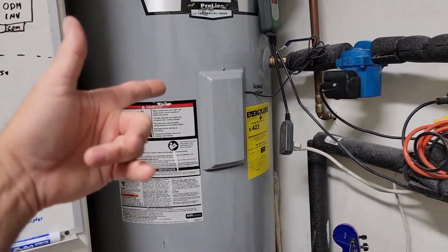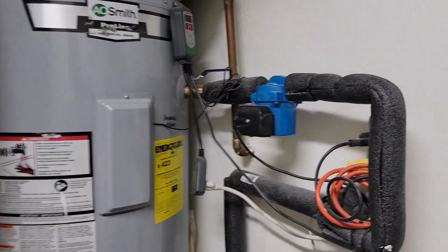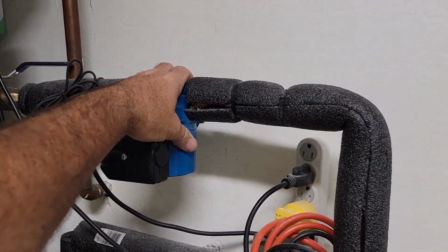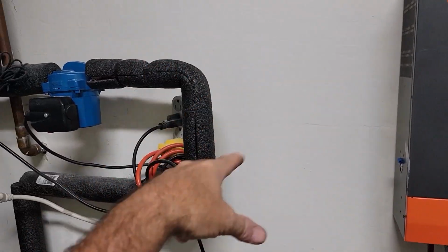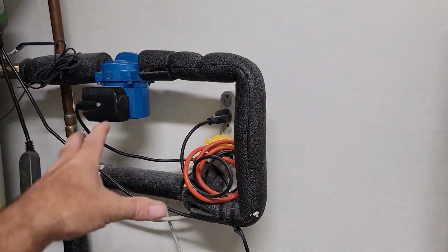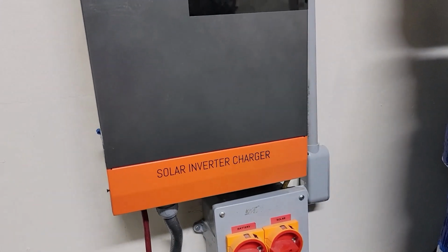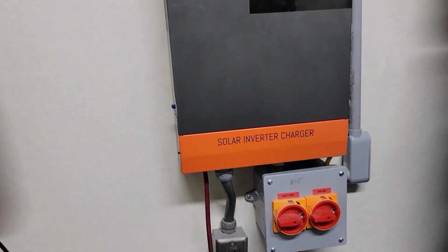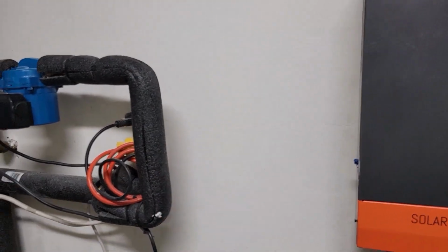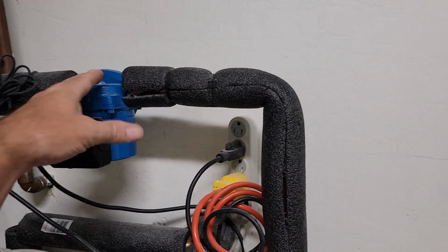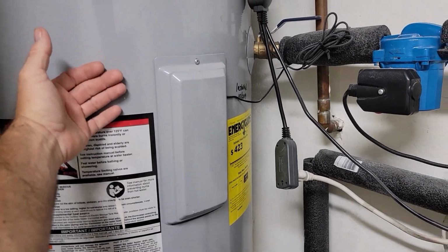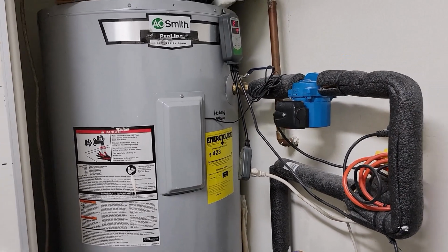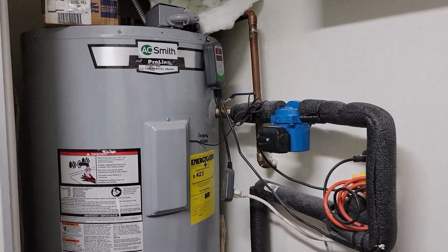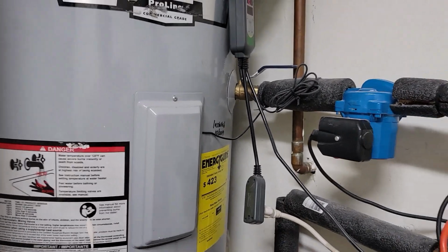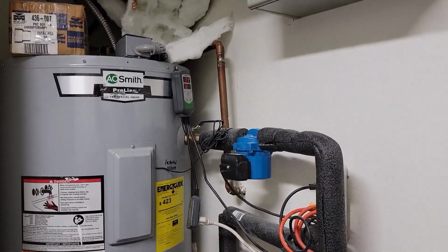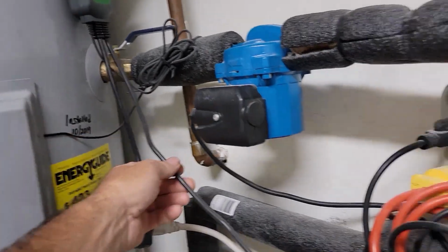So there just needs to be a limit in there with me reading the thermistor or whatever, and what my controller is going to have to do is just stop this pump. At that point the hot gas is going to go through the water heat exchanger first, and then come out and go to the outdoor coil, which runs the fan based on liquid line temp, so it will just automatically keep running fine out there. It'll just stop moving the water through and stop overheating the water heater or the storage tank. If you want to be technical, it won't be a water heater, since the heat pump is the heater. These elements are off. Hardly ran. So I might not even use this basic control anymore, which is just turning on that compressor.